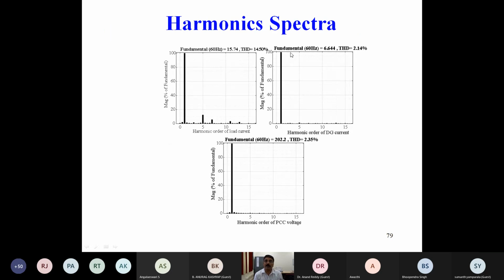The total harmonic distortion you can see here. Harmonic load current was having 14.5% harmonic. The DG current was having 2.14. And the voltage at PCC, point of common coupling, was having 2.35. That means these two are unaffected by the load harmonics.